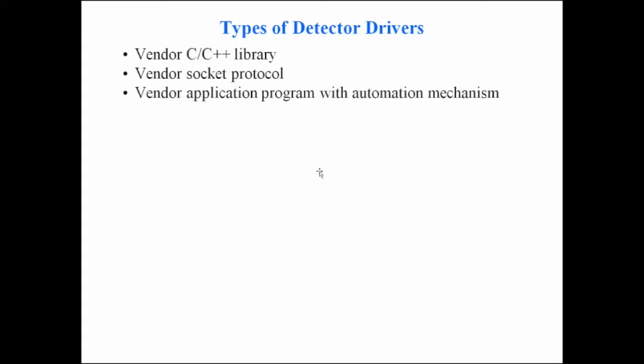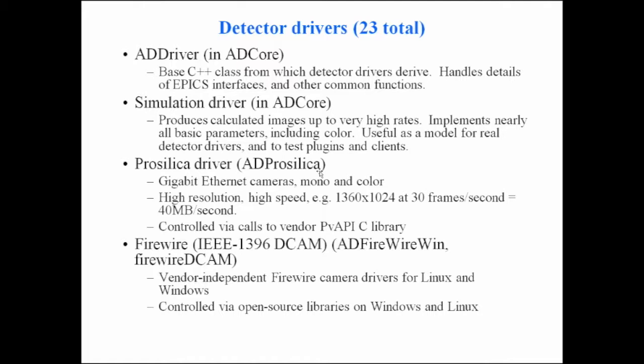Right now I counted 23 different drivers in area detector, supporting many more cameras and detectors than that because some drivers are quite generic and support detectors from a variety of manufacturers. The first driver is called ADDriver — part of ADCore — which is the base class from which all other detectors derive. When you write a new driver you inherit from this base class, which handles the details of the EPICS interface and other common functions.